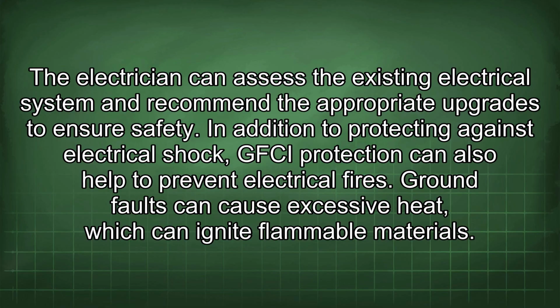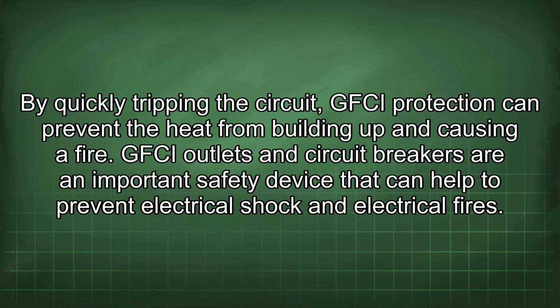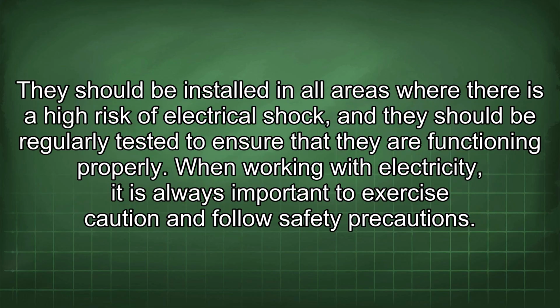In addition to protecting against electrical shock, GFCI protection can also help to prevent electrical fires. Ground faults can cause excessive heat, which can ignite flammable materials. By quickly tripping the circuit, GFCI protection can prevent the heat from building up and causing a fire. GFCI outlets and circuit breakers are an important safety device that can help to prevent electrical shock and electrical fires. They should be installed in all areas where there is a high risk of electrical shock, and they should be regularly tested to ensure that they are functioning properly.